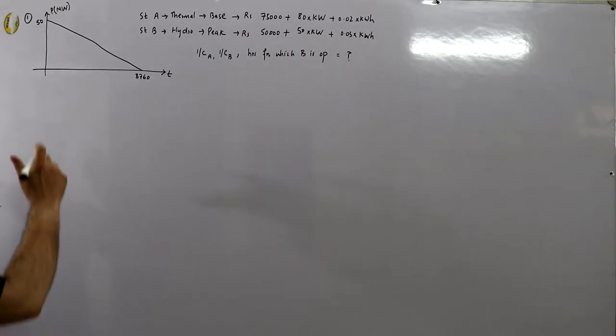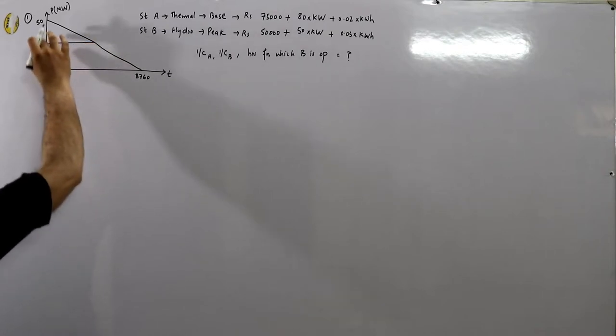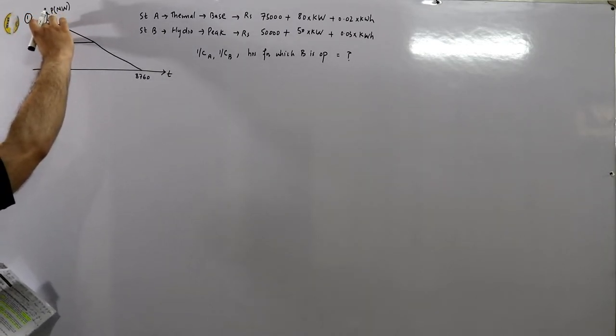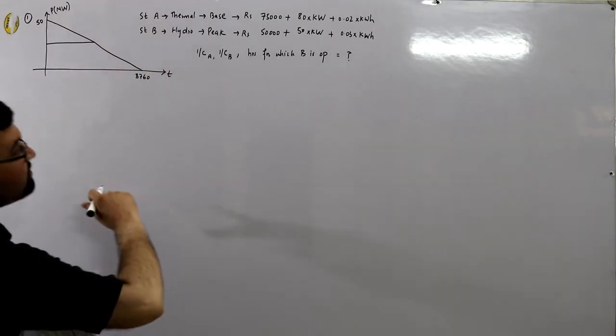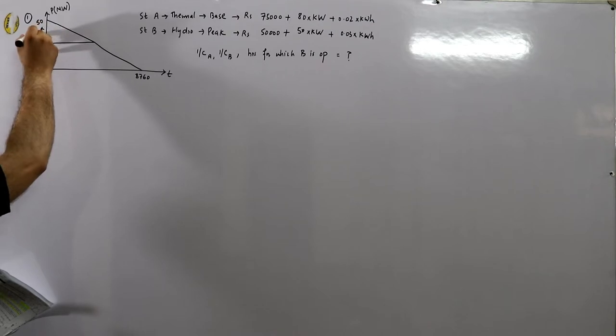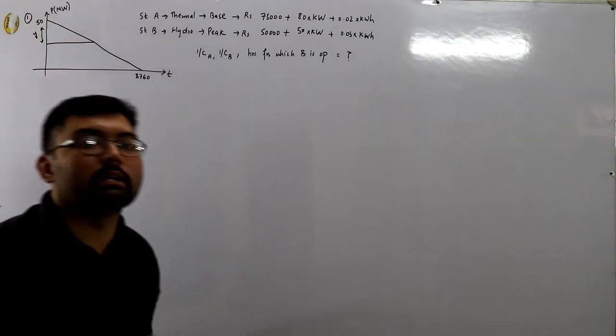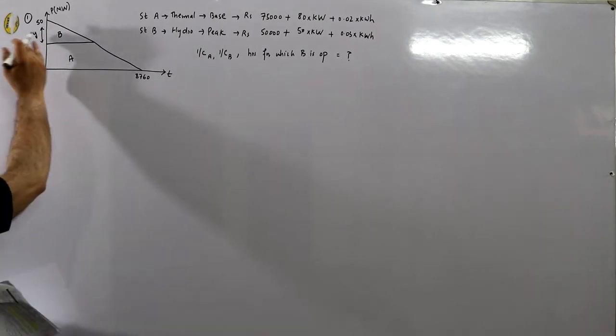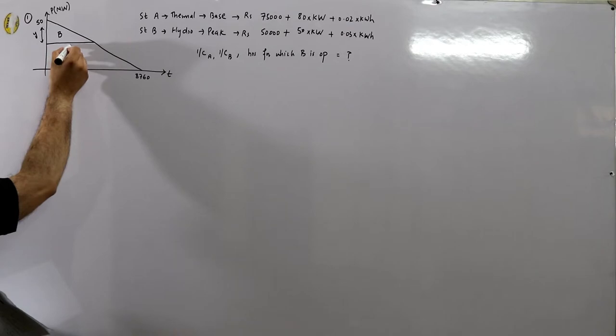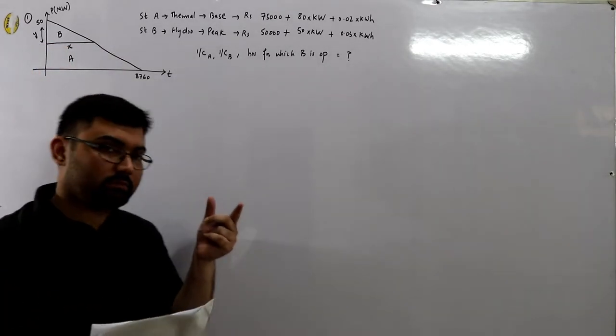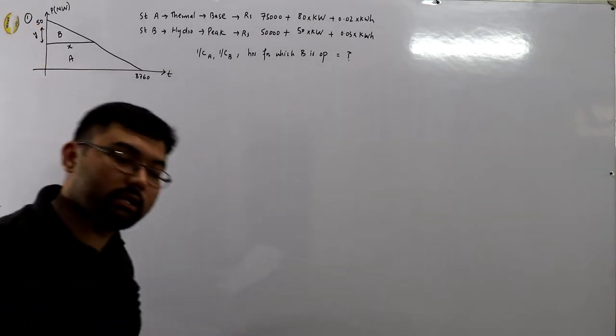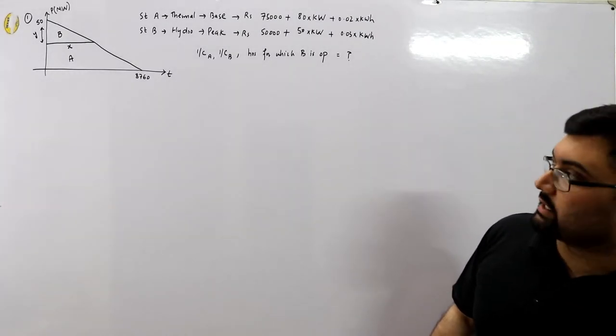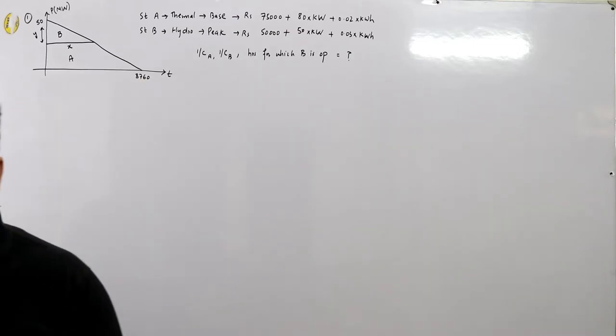We start by subdividing the load duration curve into peak load and base load regions. The peak load portion is a triangle supplied by the peak load station B. Let Y be the installed capacity of station B, and X be the number of hours for which the peak load station runs in parallel with the base load station A.